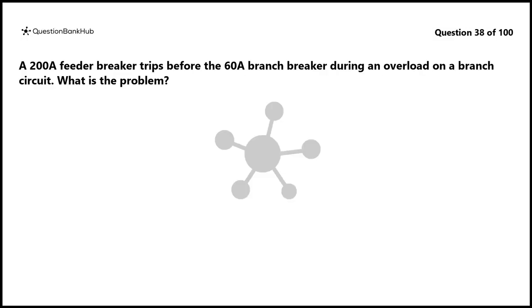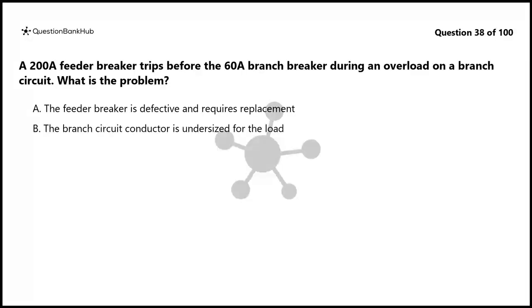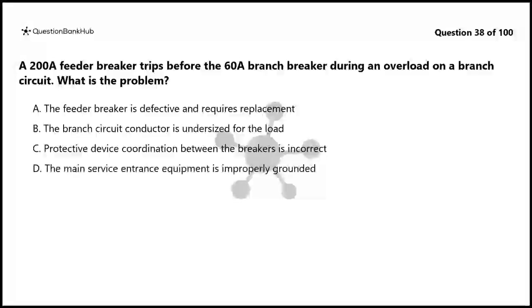Question 38. A 200 amp feeder breaker trips before the 60 amp branch breaker during an overload on a branch circuit. What is the problem? A. The feeder breaker is defective and requires replacement. B. The branch circuit conductor is undersized for the load. C. Protective device coordination between the breakers is incorrect. D. The main service entrance equipment is improperly grounded.